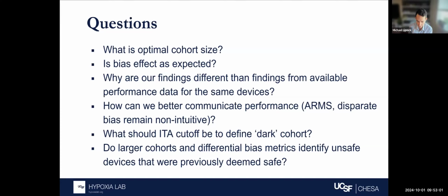The best example I could give is we have healthy volunteers who come into the lab all the time with incredibly low perfusion index as read by Masimo, or pulse percent modulation as read by Nellcor, and they're obviously well and not on pressors and have a normal blood pressure, and good perfusion systemically. So it's hard to say, but we will share what we have on that as soon as we can. Thanks. Great job with this stuff. You're welcome. Thanks a lot.